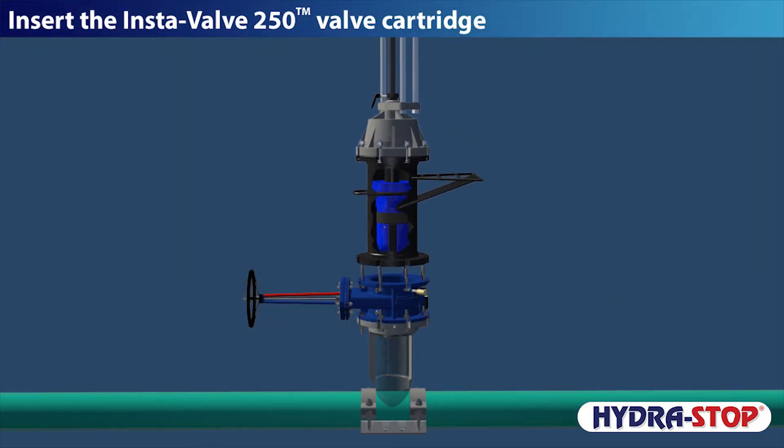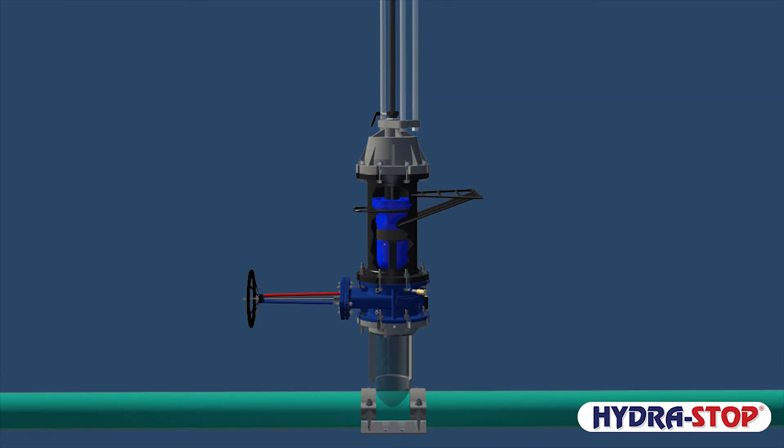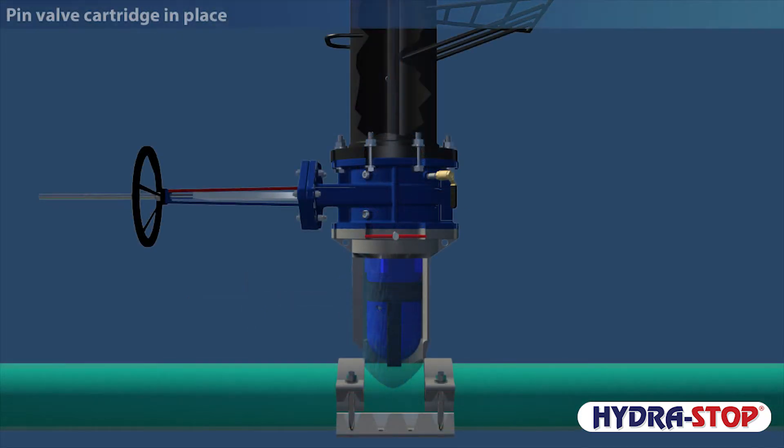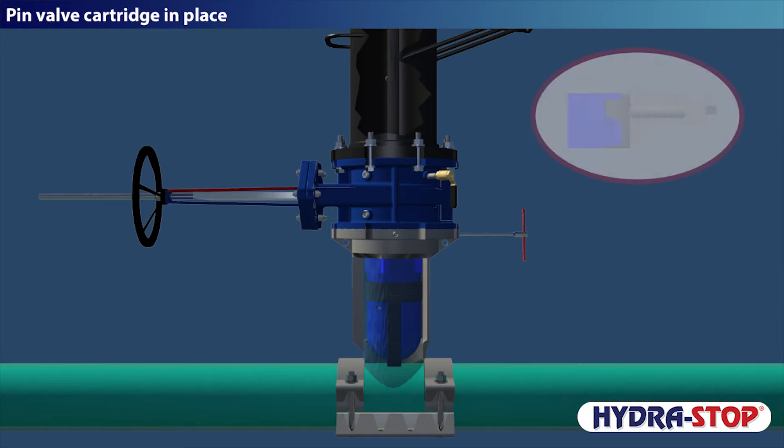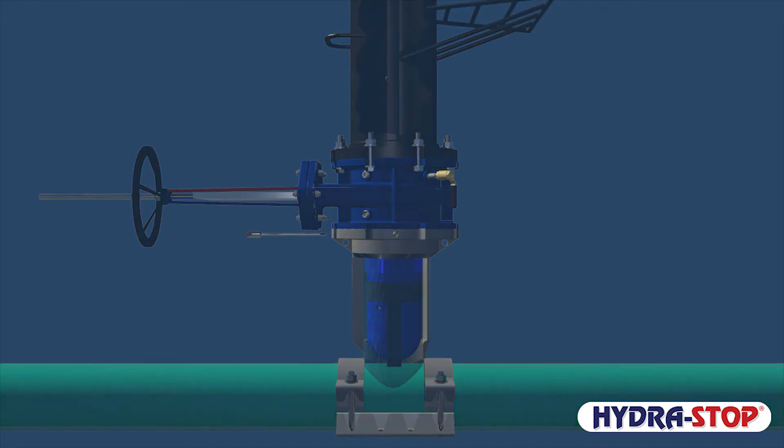Insert the Instavalve 250 valve cartridge. Pin the valve cartridge in place. Compression pins are backed out one quarter of a turn to allow the valve cartridge to self-center.